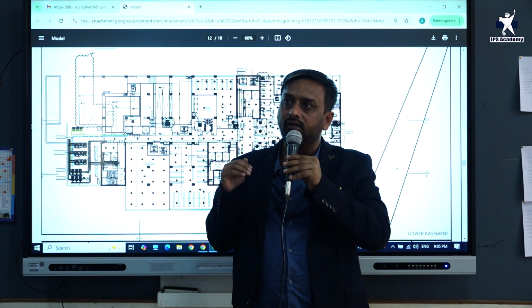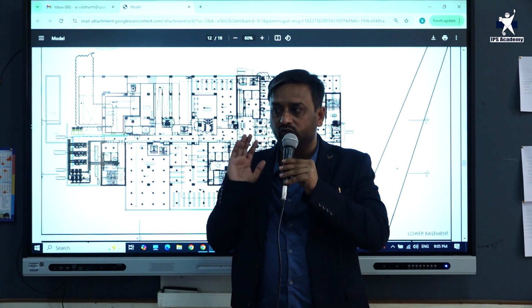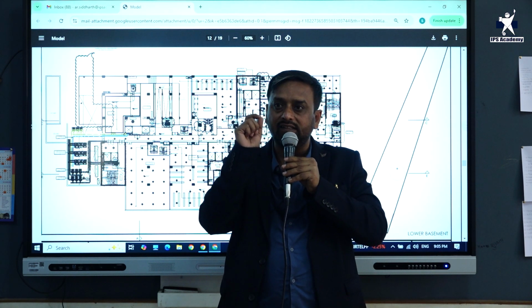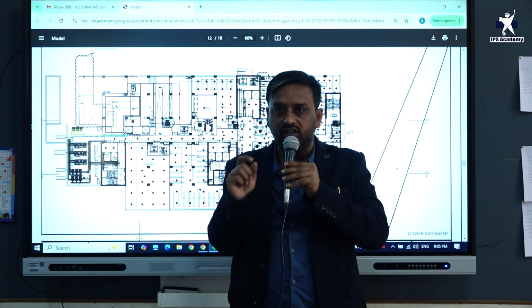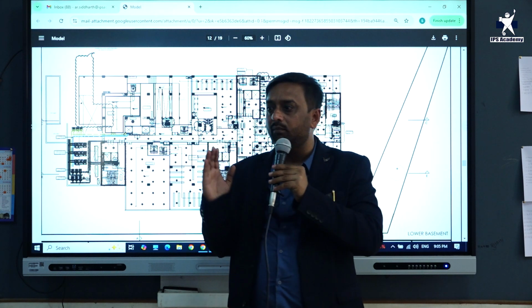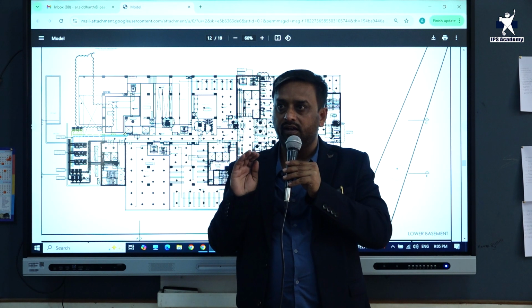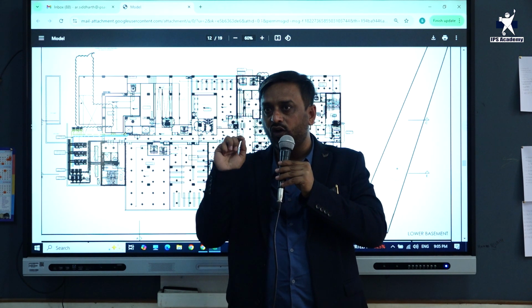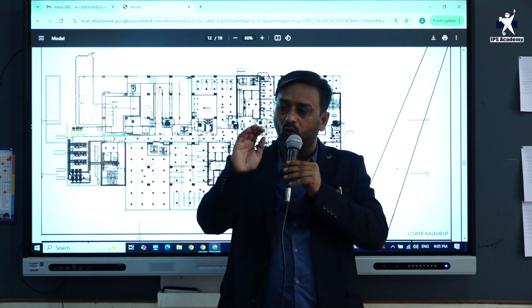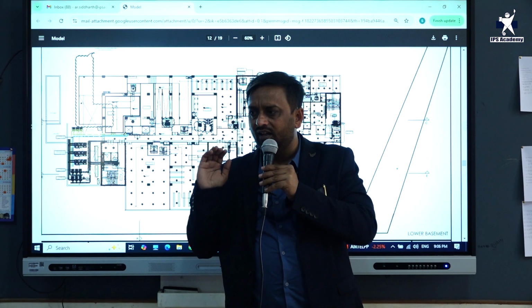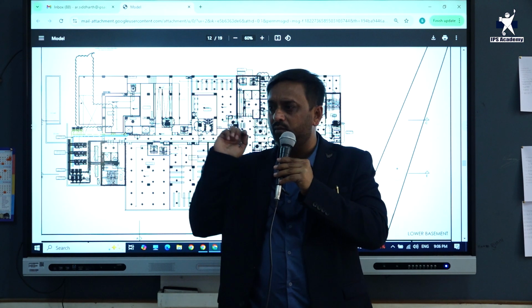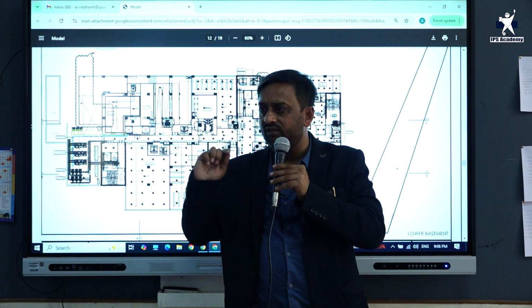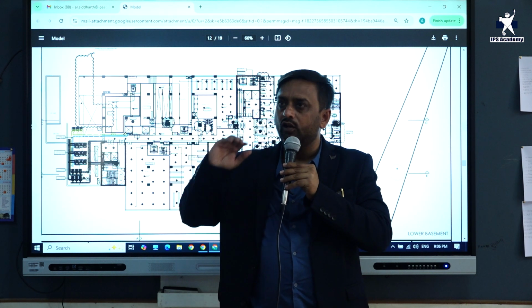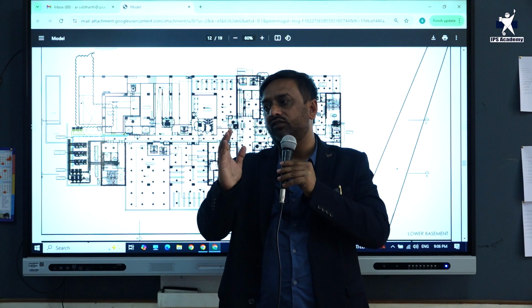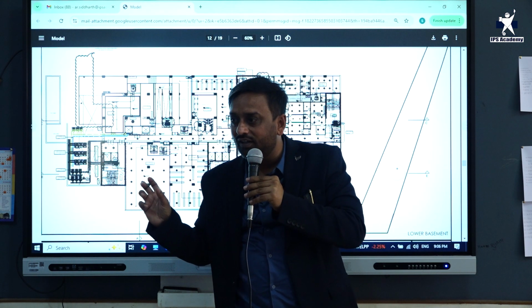As I discussed, the design starts before 6 months of groundbreaking, and these cutouts are established within the coordination of the architect and MEP consultant on the very first day. To ensure that the cable length, if we talk about low voltage, we are using Cat6. Cat6 has a limitation of 90 meters to transfer the data, otherwise you will have to go with fiber. So within 90 meters of distance you should have one ELV room.